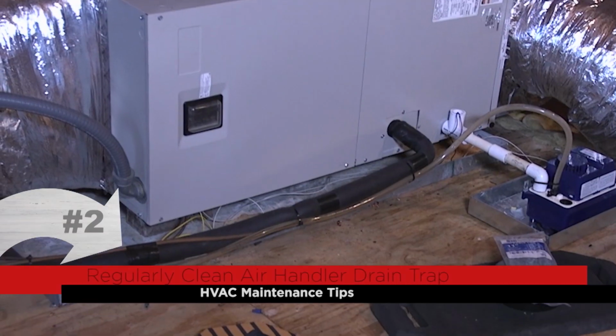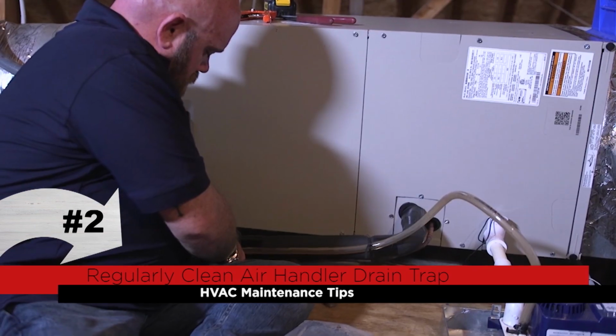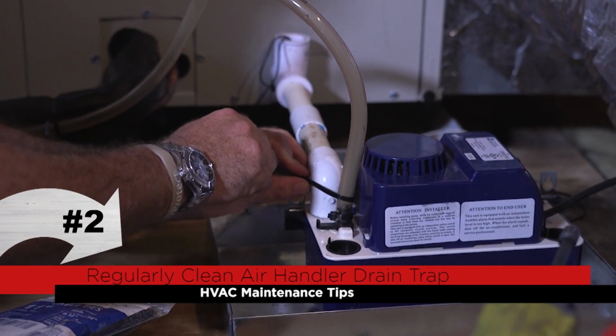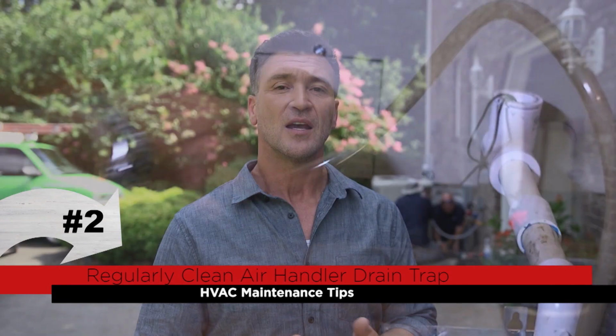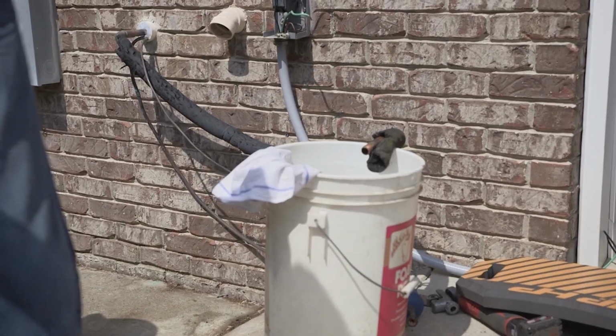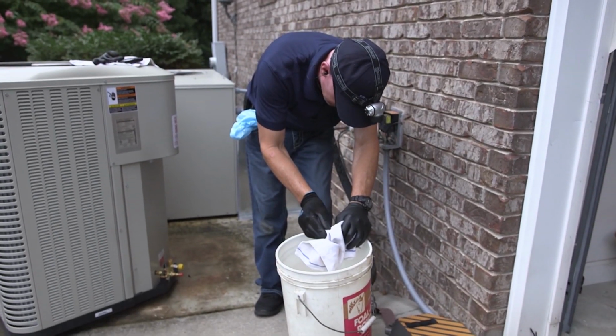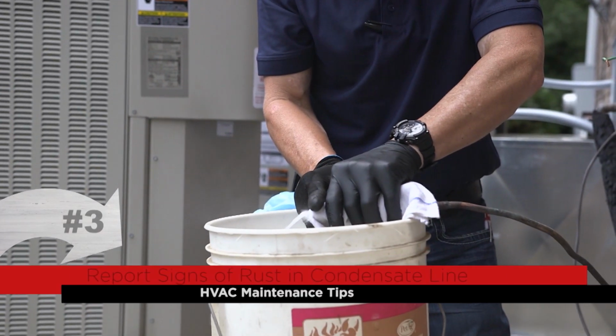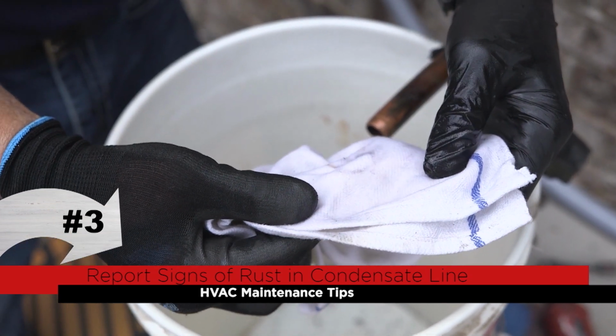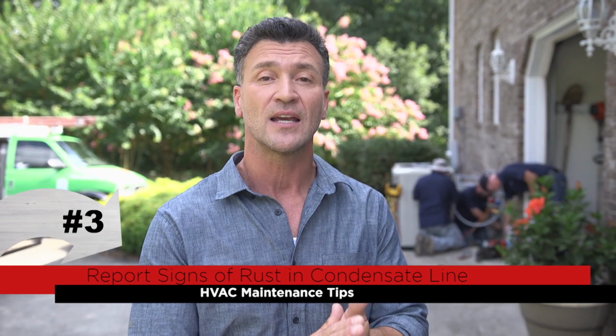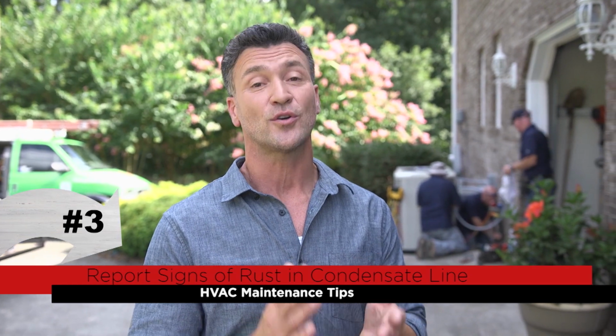Now the second one would be cleaning your drain trap. So the drain trap is the PVC line that's coming off of your air handler upstairs in your attic. Pour just a little bit of bleach in that line, maybe every 3 to 6 months. And what that will do is that will clean that line out and make sure that no clogs will occur. Number 3, your condensate line that's coming from the air handler in the attic. That pipe will clean all that water out. If you see rust in that line, anywhere around it, either on the brick or on your vinyl siding, what you want to do is that you want to call your service technician before anything bad can happen.